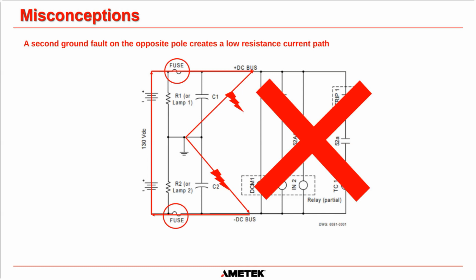If you get a negative ground fault and a positive ground fault at the same time, basically you are creating a direct short between the positive and the negative. And if you see here, we've got two fuses in this circuit, and there are always going to be fuses to protect if there is a fault in any of the coils back here, okay? So if you have a direct short, a positive and a negative ground fault at the same time, one of these fuses is going to blow.